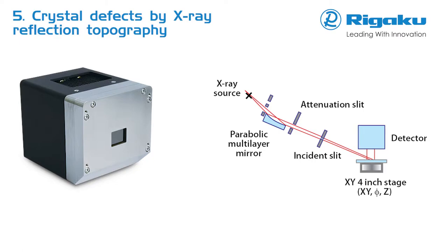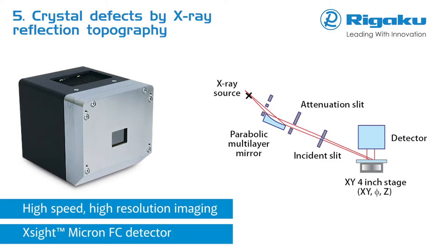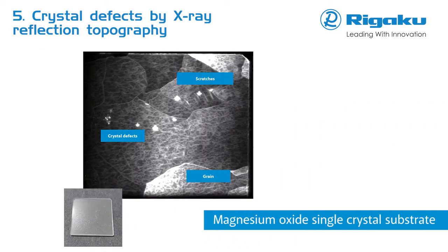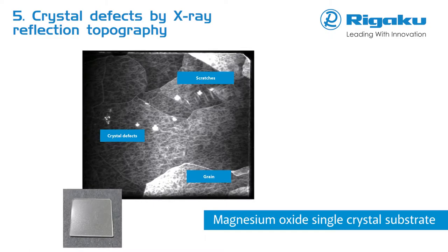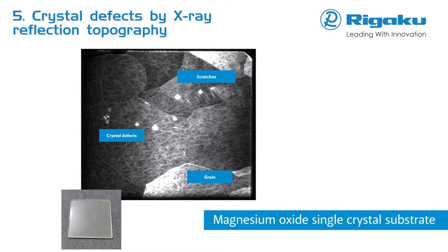SmartLab, equipped with the Xsight Micron FC detector, is now capable of performing fast, high-resolution X-ray topography on single crystal surfaces, providing visual images for quality assurance or quality control of crystal defects. A homogeneous sample with a regular crystal lattice would yield a flat image. Intensity modulations, known as topographic contrast, arise from irregularities in the crystal lattice, originating from various kinds of defects, like those shown here for a magnesium oxide single crystal substrate.